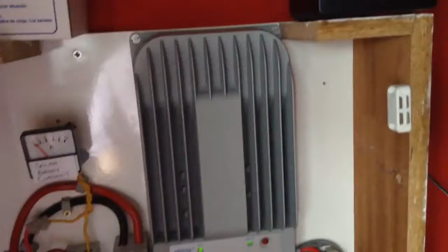One thing about my cabinet, you'll be wondering why there's a big hole in the bottom and a big hole in the top. The idea is that when you shut the door, the electronic equipment handles power and produces heat, and the heat needs to escape. We implement this simply with convection—hot air rises up through the hole in the top and draws cooler air in at the bottom. So it's just a passive cooling system.